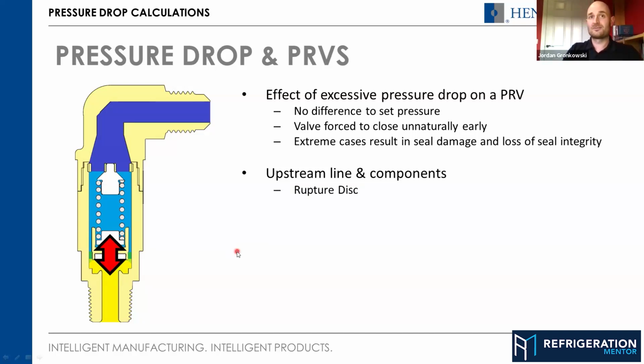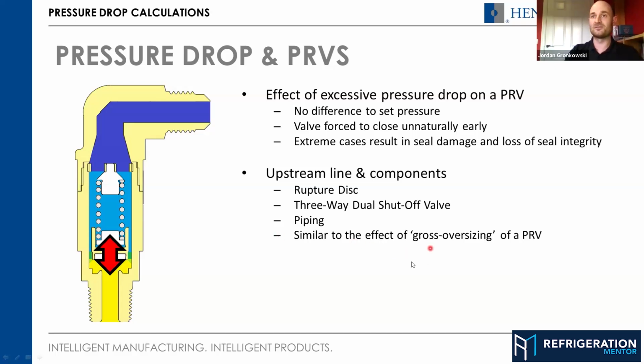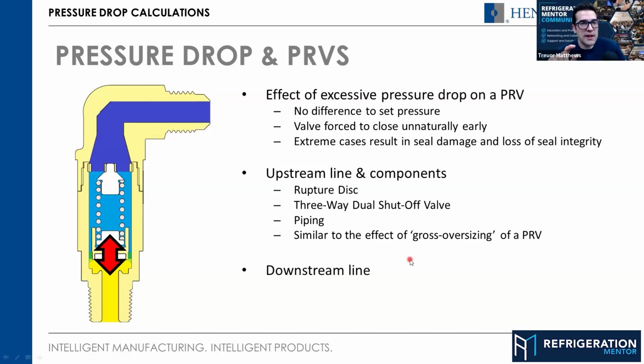So what can cause that? Things like rupture discs that are incorrectly sized, three-way dual shutoff valves that are incorrectly sized, and obviously piping that's too large or too long or too small in diameter. And again, similar to the effect of grossly oversizing the PRV. So basically, we're saying that if the rupture disc or the three-way valve is sized incorrectly, the pressure will build up and it'll open, but then it'll close too quickly. Is that correct? It'll close because the pressure it sees disappears as soon as the flow starts. With its restriction of flow, it sees less pressure, so it closes. But then the flow stops, so the pressure increases again.